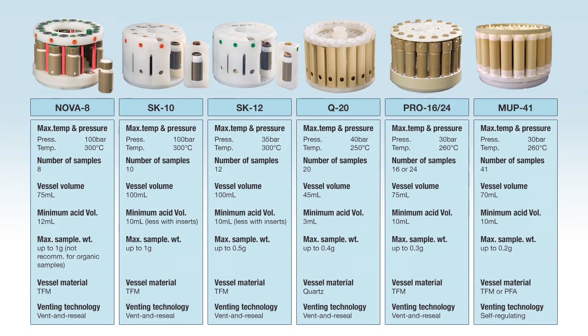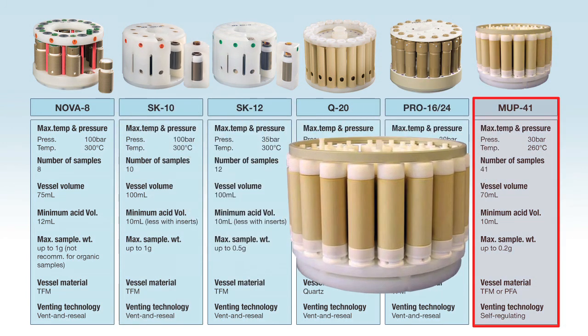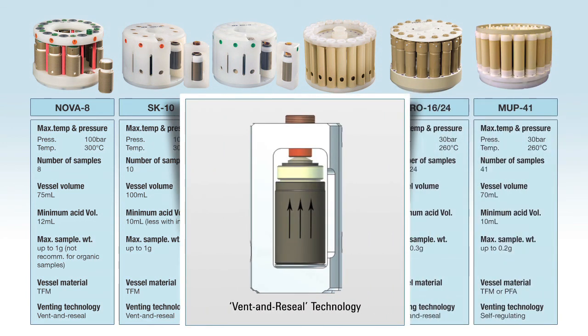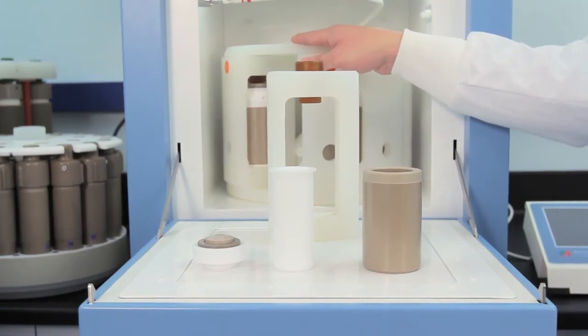The Ethos 1 has the widest range of rotors and vessels to meet every application, including a 100 bar high pressure rotor and high capacity 41 position rotor. Each of these rotors use Milestone's patented vent and reseal technology and can interchangeably be used in the same Ethos without need for changes or upgrades to the system.